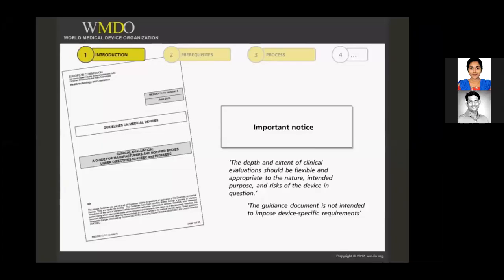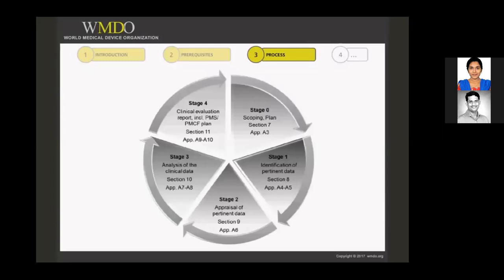The manufacturer needs to make the necessary risk considerations and weigh these carefully in preparation for the conduct of the clinical evaluation. Herewith a figure from a standard outlining the different stages of a clinical evaluation of existing data. We will review more in depth each of these stages throughout this course. Each of these stages represents an action step and as such needs to be documented in the clinical evaluation report. Stage 0 includes the clinical evaluation plan, including the scope of the clinical evaluation. Stage 1 would be documented using a search protocol and justification for the criteria elaborated of such protocol. Stage 2 should include an appraisal plan and the results thereof justifying to what extent identified data are pertinent. Stage 3 includes the analysis and conclusions reached.